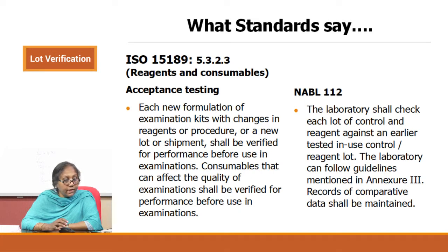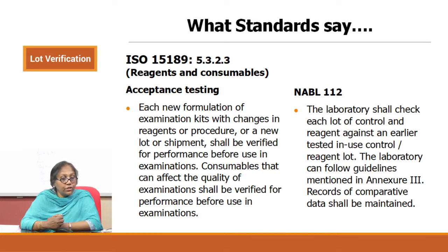Consumables that can affect the quality of examination shall be verified for performance before use. NABL 112 in addition says the laboratory shall check each lot of control and reagent against an earlier tested or in-use control or reagent lot.